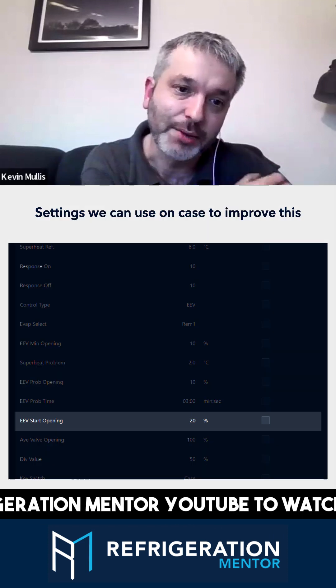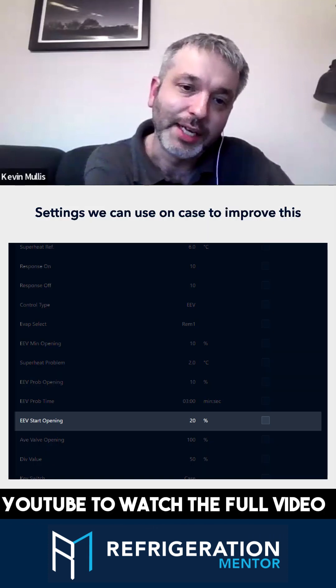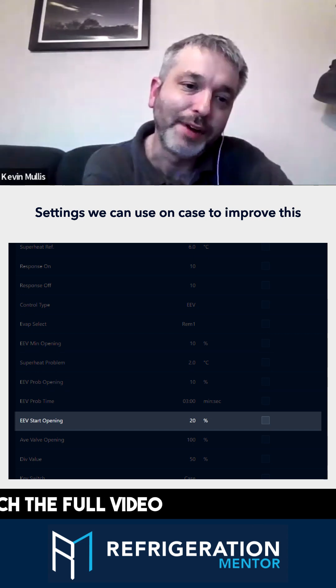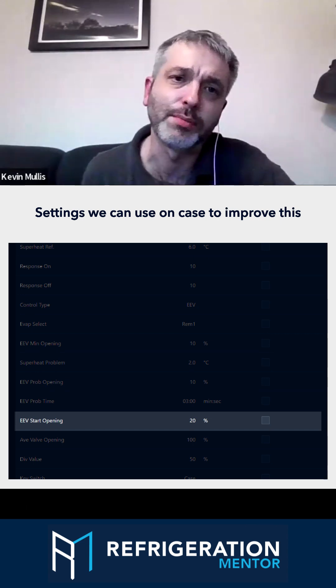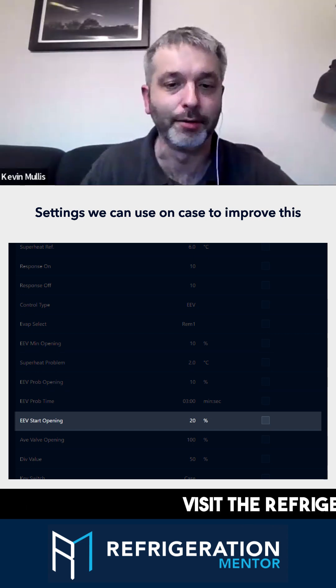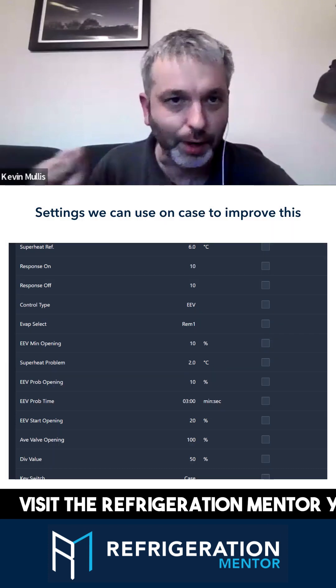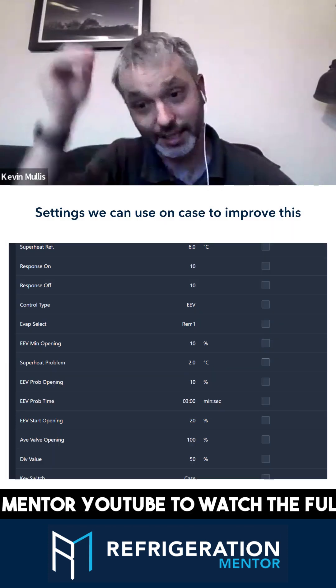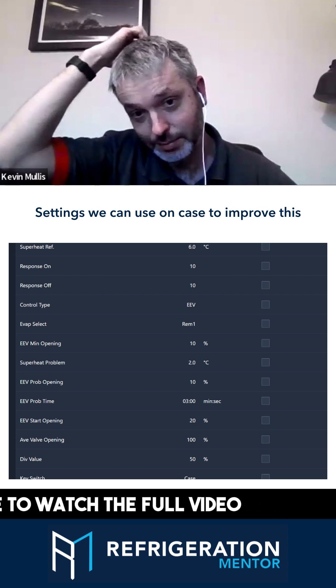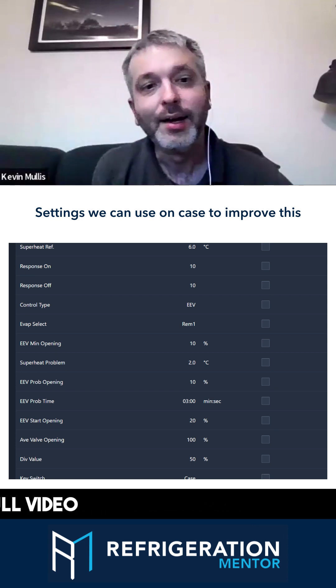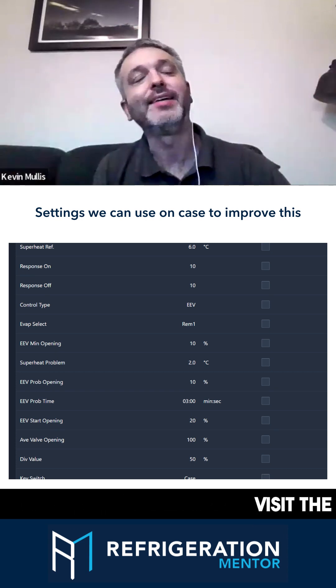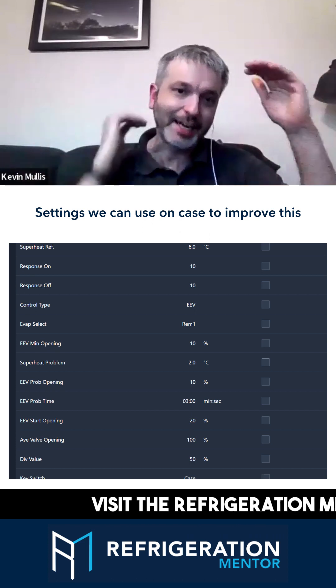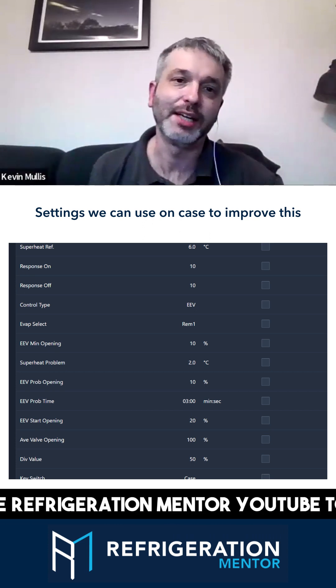Again, start opening there is the other key one. As I said, it's very tempting on systems where it controls on probes to rack that number really high and bomb a load of liquid in when you start. With a transducer, you don't need to. Actually, I checked the latest version of RDM's manual and they're now recommending you set that number to zero for things like the superheat problem.